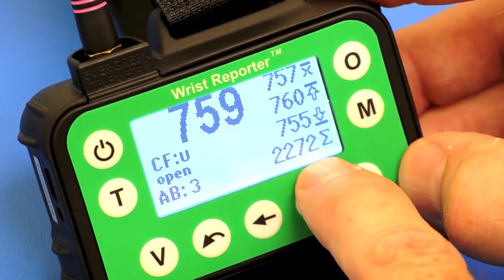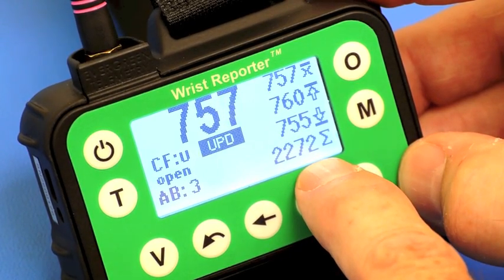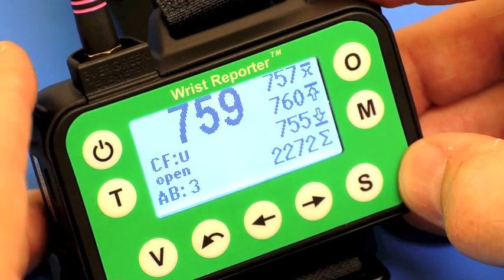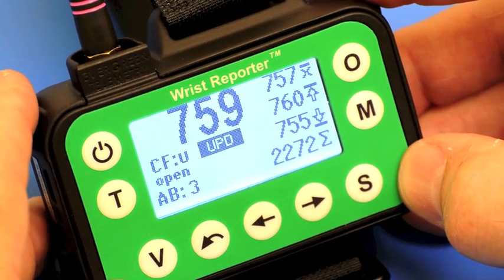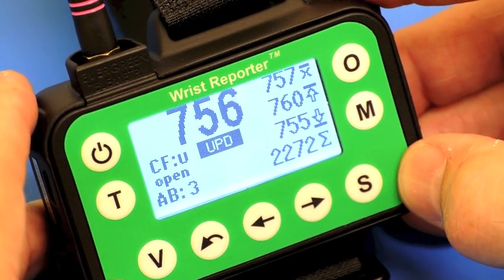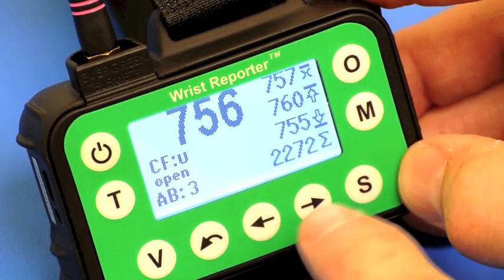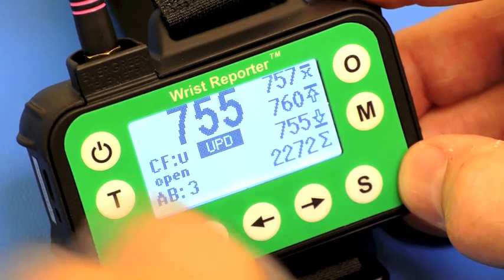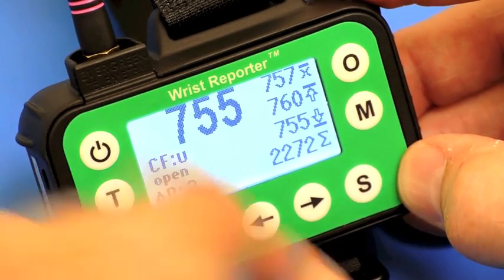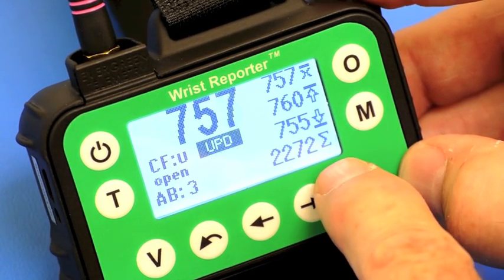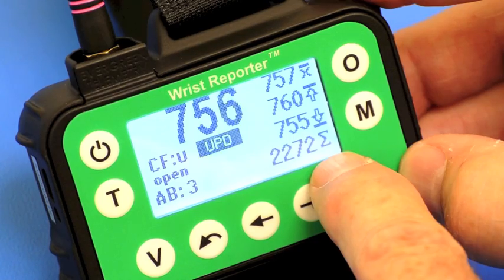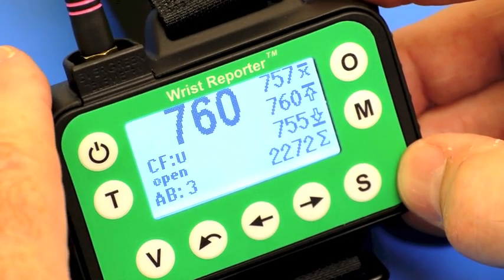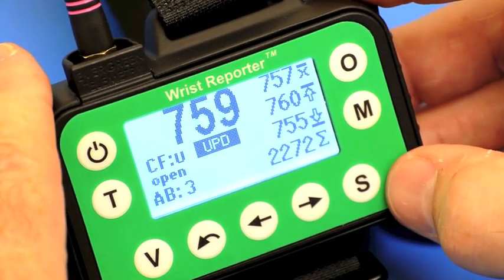Also in this mode we have available a sum or total feature. If I press S again to capture another reading, and press S again to capture another, I've now stored three readings. The sum of those readings is 2272. For operations doing a survey of a facility, this is a great way to quickly get an estimate of the supply air or return air by just storing those particular diffuser readings.